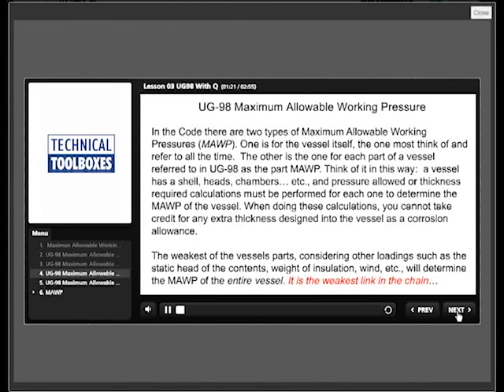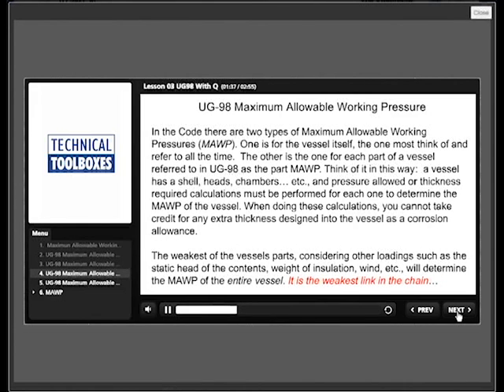In the code, there are two types of maximum allowable working pressure, or MAWP. One is for the vessel itself, the one most think of and refer to all the time. The other is the one for each part of the vessel, referred to in UG-98 as the part MAWP.